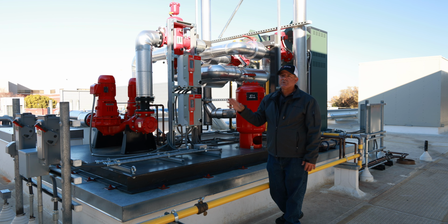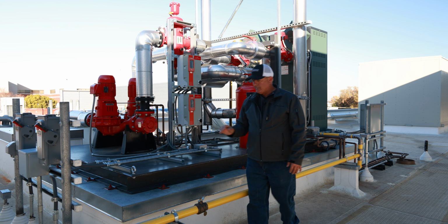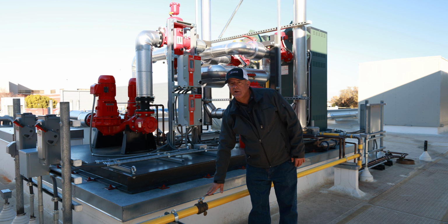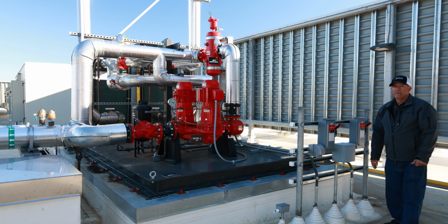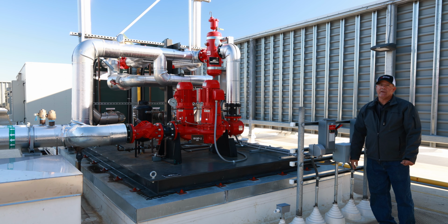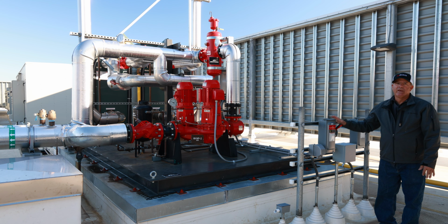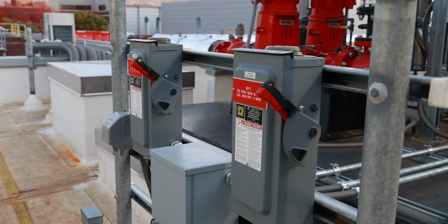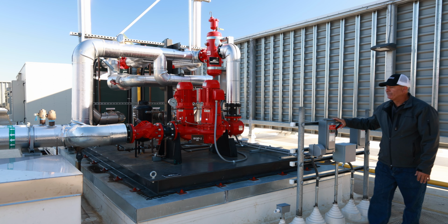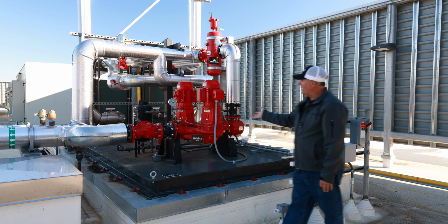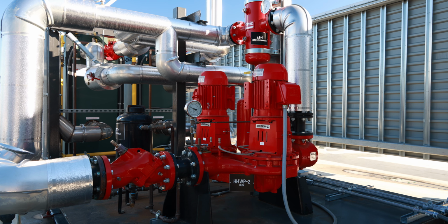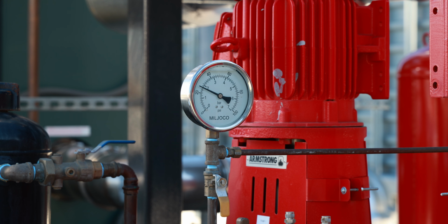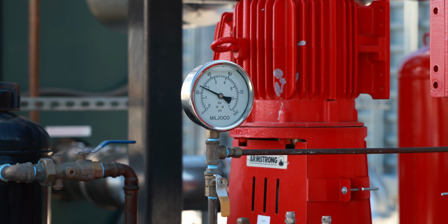Okay, we're going to walk around and show you some disconnects. Before I get there, this is the main gas shutoff for the boilers. Okay, so a little farther around the back side of the boiler, these are the disconnects for the primary pumps and the boilers. Your circulating pumps for the heating hot water loop, which also feeds domestic hot water.